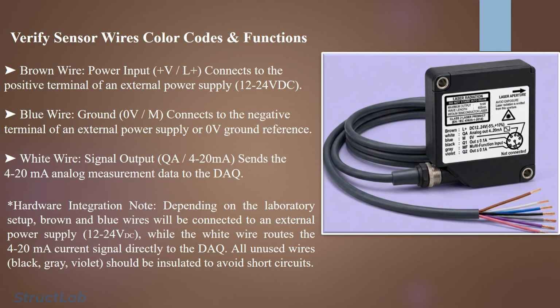Step 2. Map out the sensor's wire color codes and their functions. The brown wire acts as the positive power input, connecting directly to the positive terminal of your external power supply. The blue wire serves as the 0-volt ground return, connecting to the negative power supply terminal. The white wire carries the 4 to 20 mA analog signal output, routing real-time measurement data straight to your DAQ input channel. Together, the brown and blue wires power the sensor, while the white wire feeds the measurement signal into your acquisition system. Any unused wires should be properly insulated to prevent short circuits.